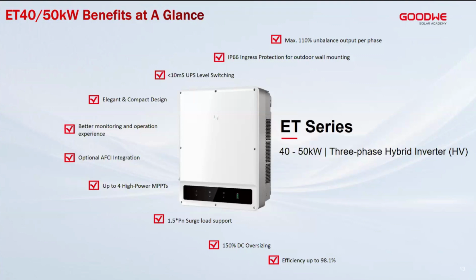Now, because most loads, not all, but some of the loads in the C&I sector might be inductive in nature, there is a need to have surge support. The ET series is able to support a surge load of up to 1.5 times the inverter rating for 10 seconds. That is actually enough to cover the starting inrush current for the inductive loads. That is one of the unique features of the ET series.